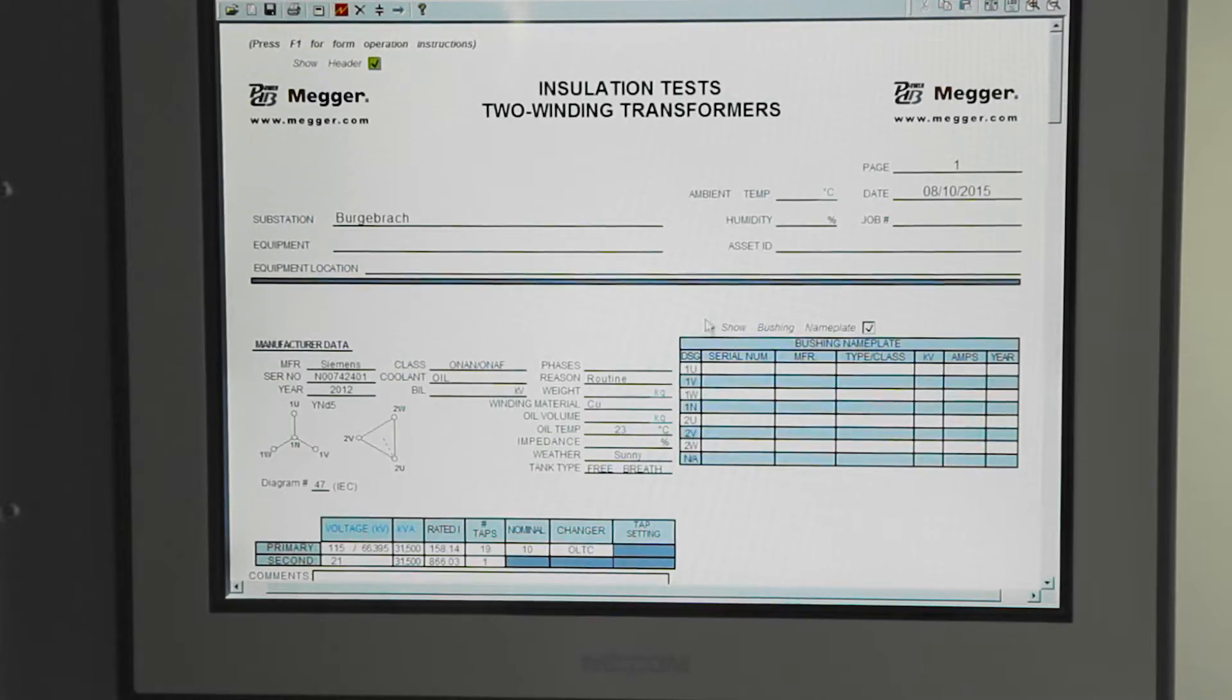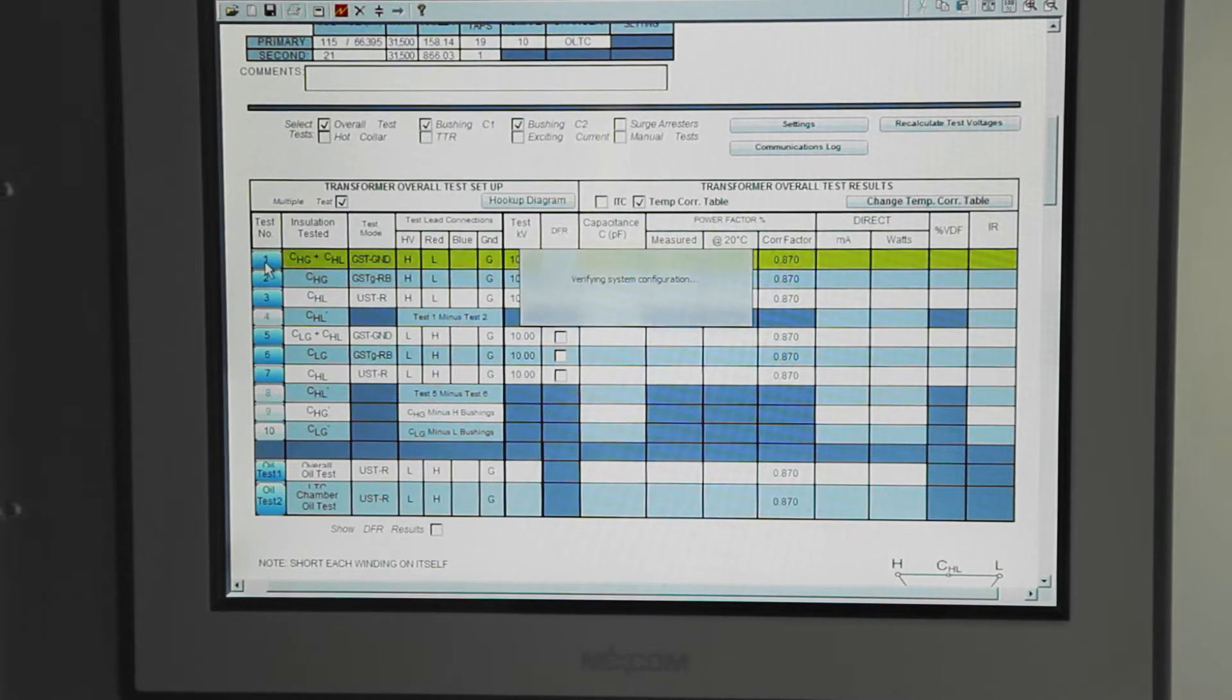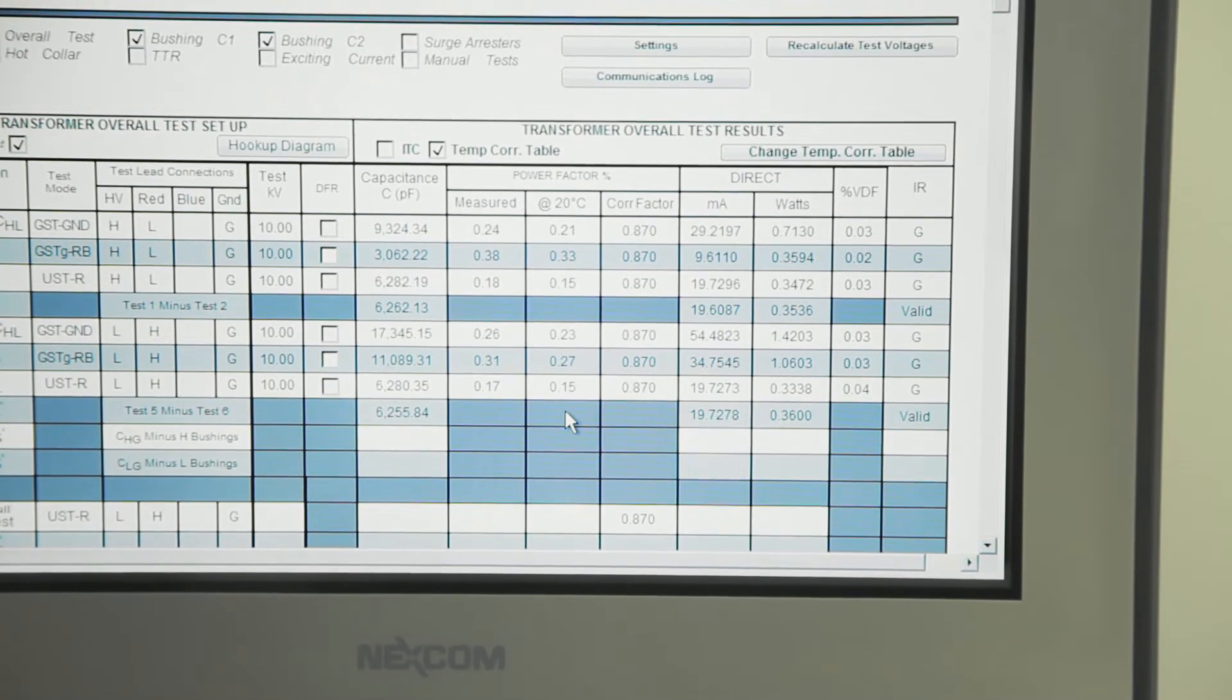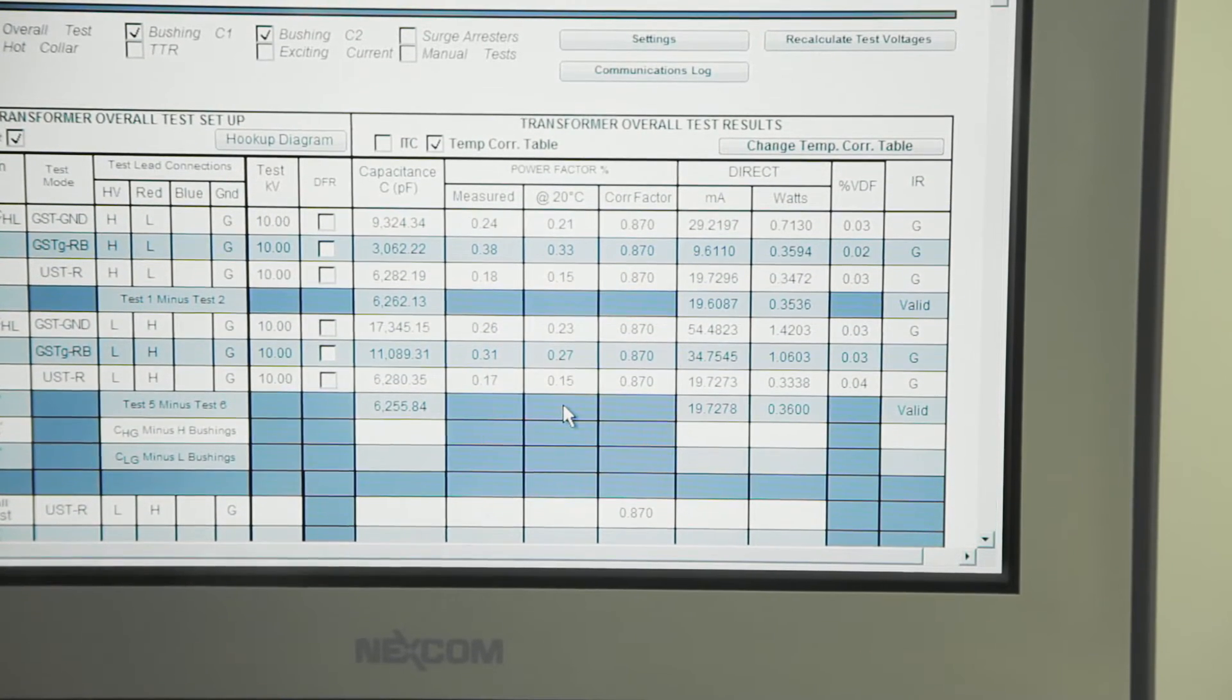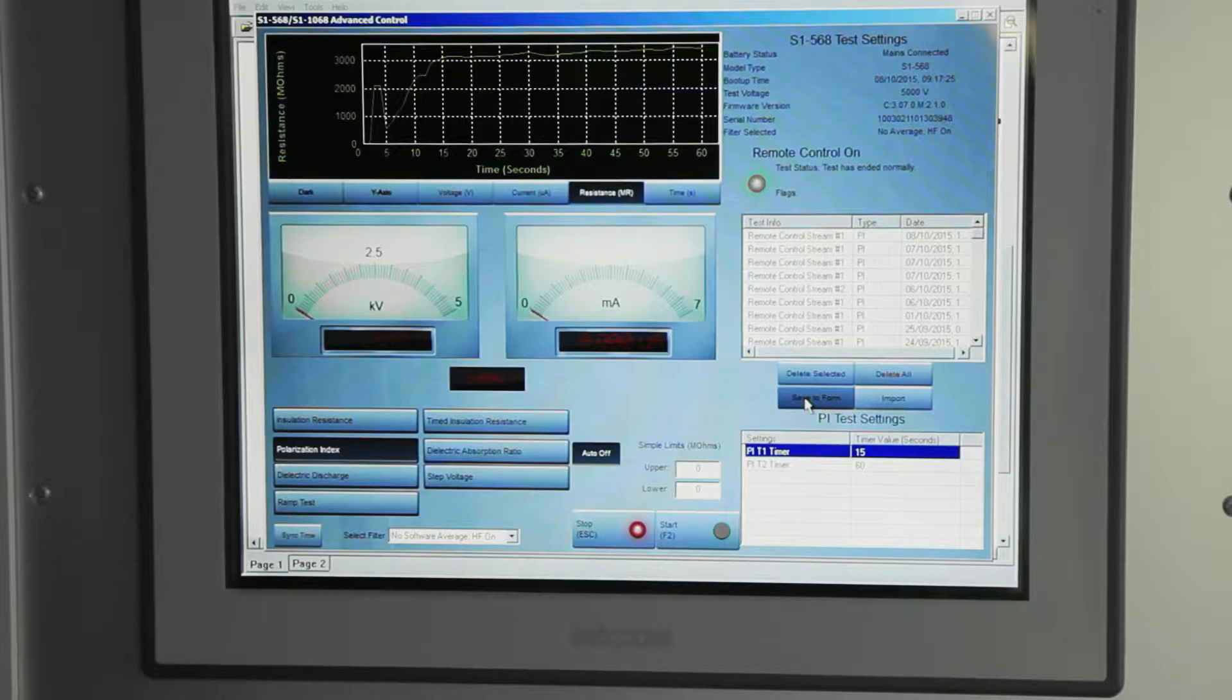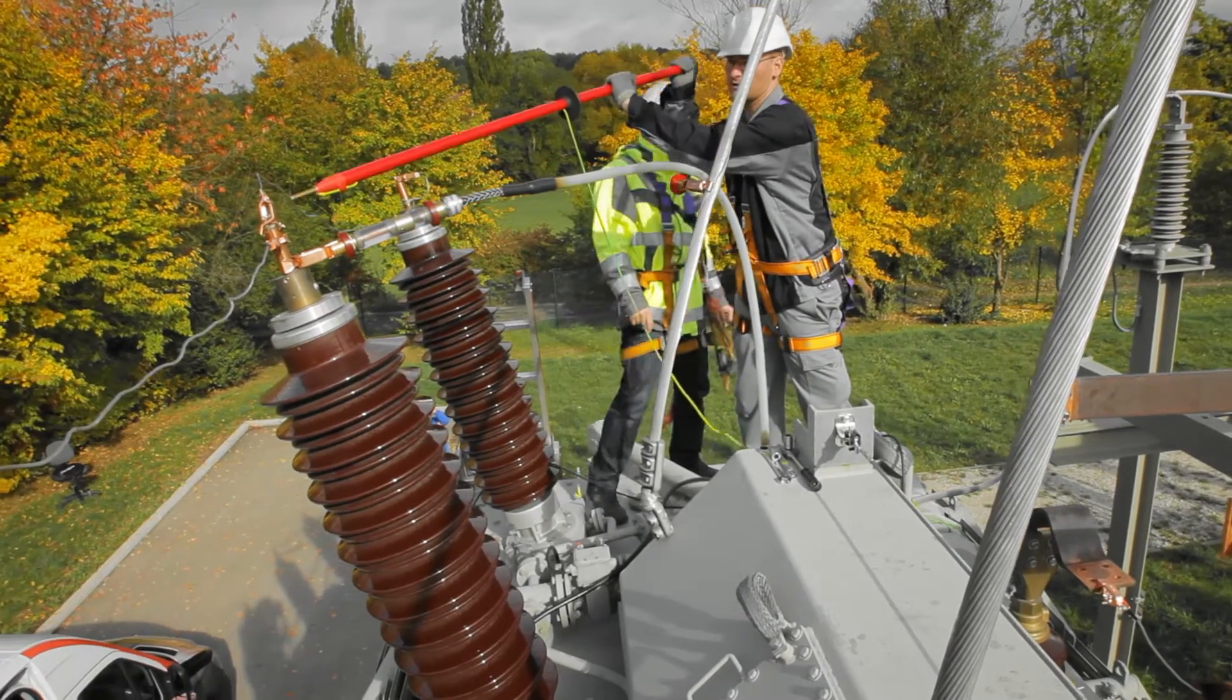Insulation tests can identify the deterioration of electrical insulation. High voltage AC tests measure the dissipation or power factor and capacitance of transformer windings and bushings. Insulation resistance is determined between windings and tank using a high voltage DC source.